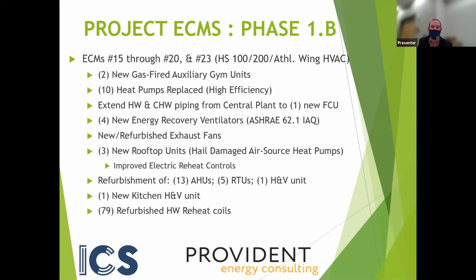The scope of work is similar, except originally these 10 heat pumps were going to be replaced with 4-pipe fan coil units, running hot water and chill water from the central plant to these areas. Through analysis of the geothermal system's capacities and loads, we determined we have enough capacity in the geothermal loop, but the extent of the piping runs got pretty significant. So for the 10 heat pumps, it was determined that installing the 4-pipe system wasn't favorable.